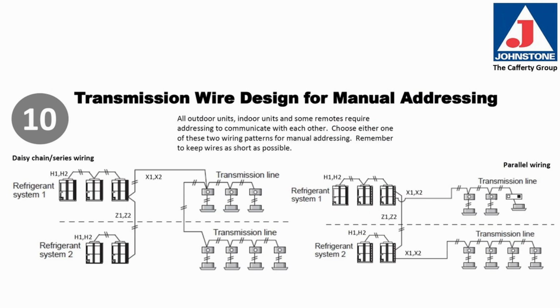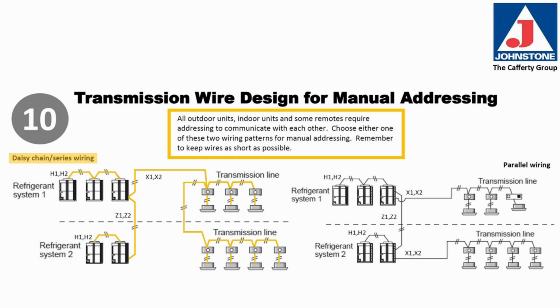Transmission wire design for manual addressing. All outdoor units, indoor units, and some remote controllers require addressing to communicate with each other. Choose either one of the two types of wiring patterns for manual addressing. Remember, keep your communication wire as short as possible. On the left, you see a daisy chain or series wiring, meaning all of the outdoor units and indoor units are in series with a daisy chain, one in and one out each indoor unit.